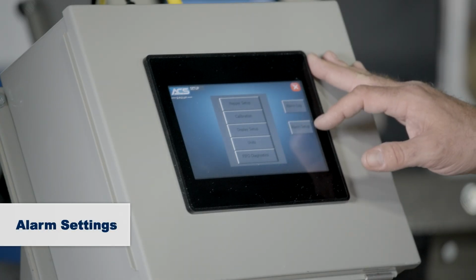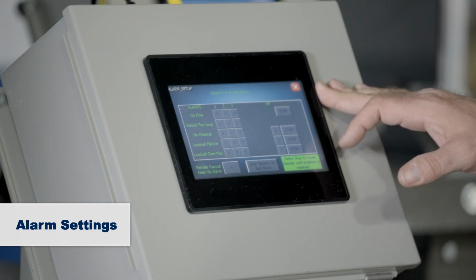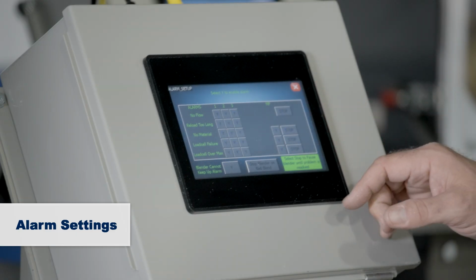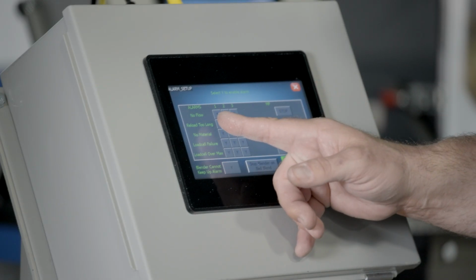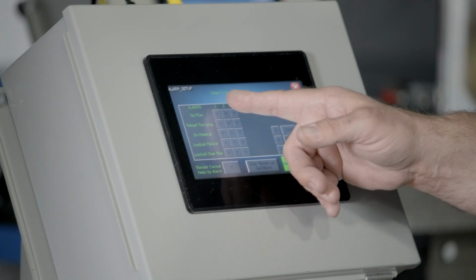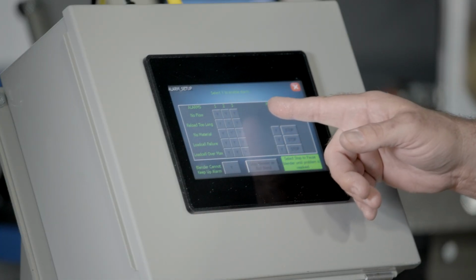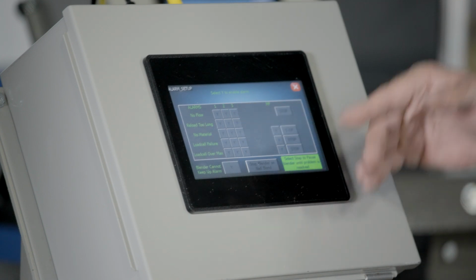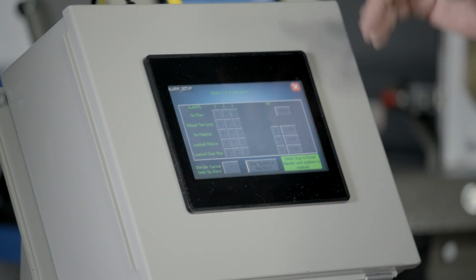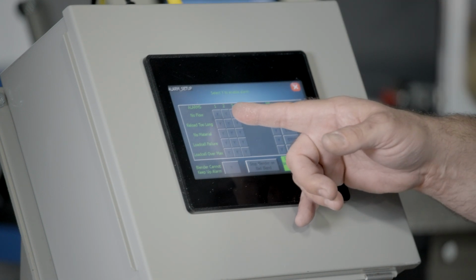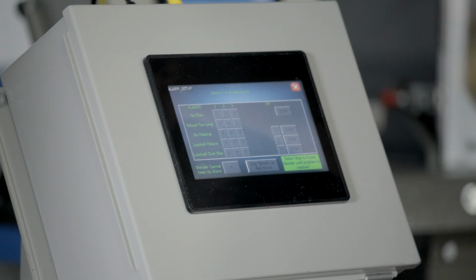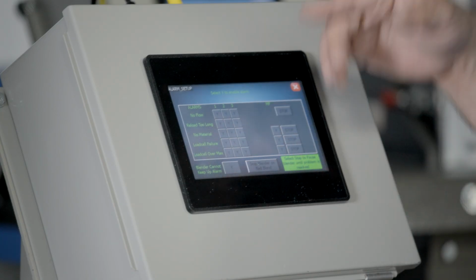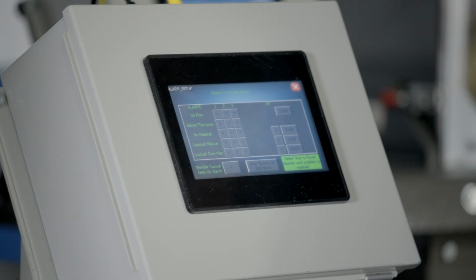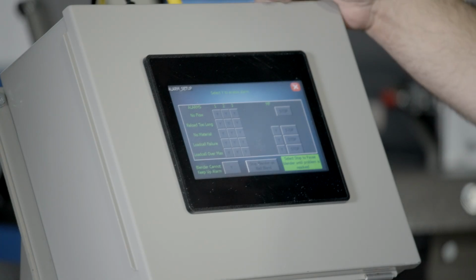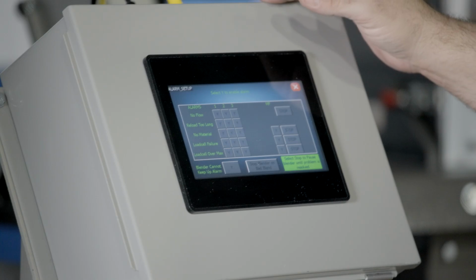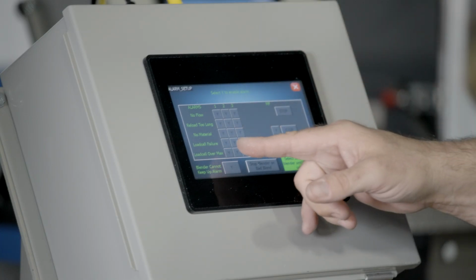Next we'll look at alarm settings. We have a couple different settings, and you can see they're for hopper 1, 2, 3, and then your mass flow is over here. We have no flow, which means we're not seeing any weight loss coming out of the feeder. You can have that set to yes for alarm or no. We also have reload too long, which means we're not getting material into your weigh hopper from the hopper above it. It could be that your loading system's off or there's no material available to your loading system.